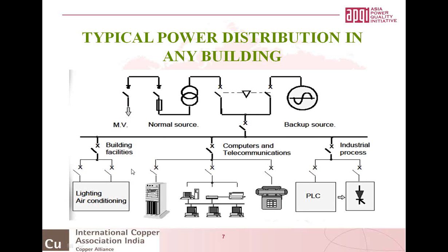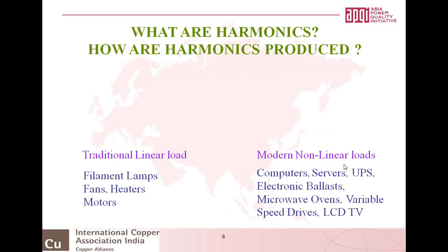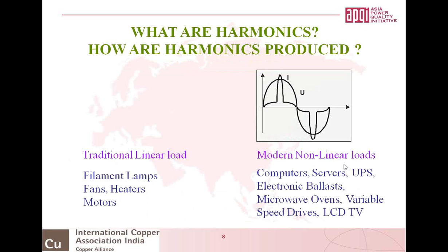Now if you see a typical power distribution system of a building, there is a transformer, a generator as a backup source, then lighting and air conditioning in the building, computers and telecommunication loads, and PLCs if it's an industrial facility. So you can see that in any distribution system there would always be a presence of harmonic producing loads. You have already seen how the harmonic waves get distorted, so I'll skip through that. What are the economic impacts of these harmonics?